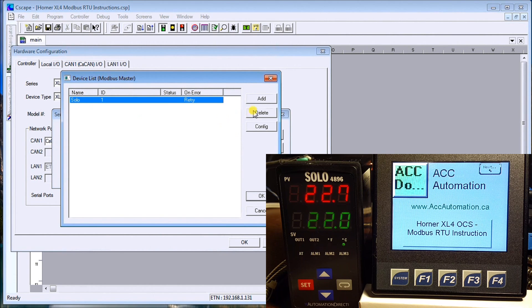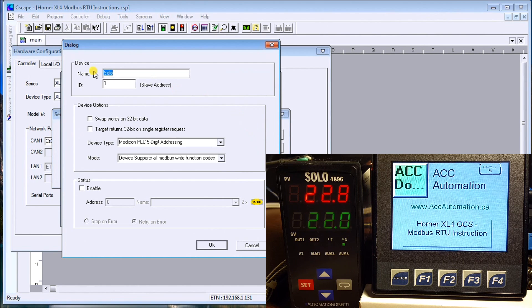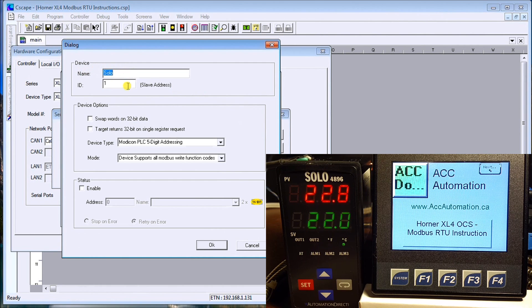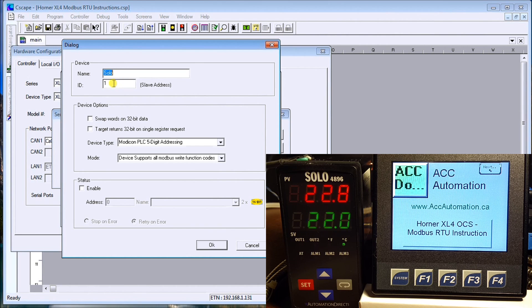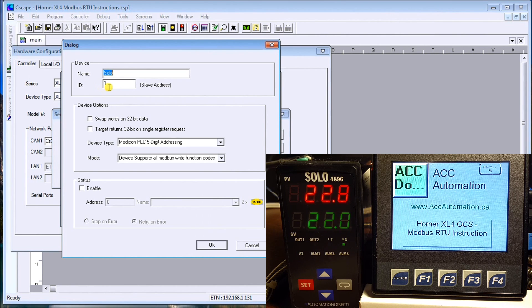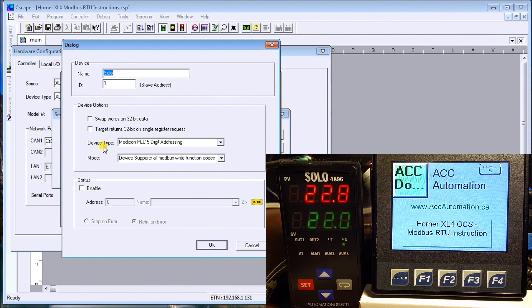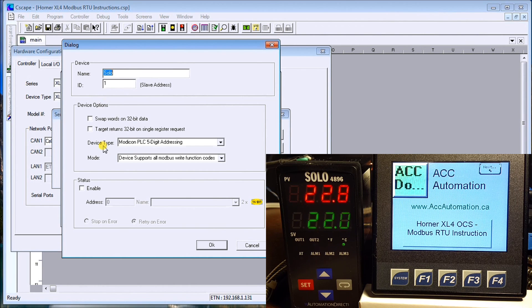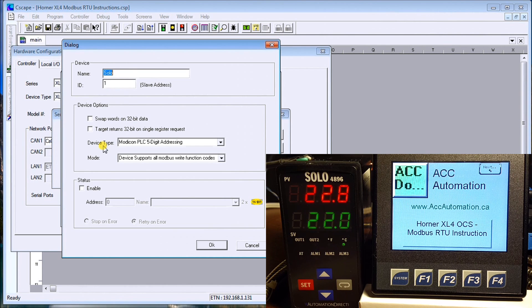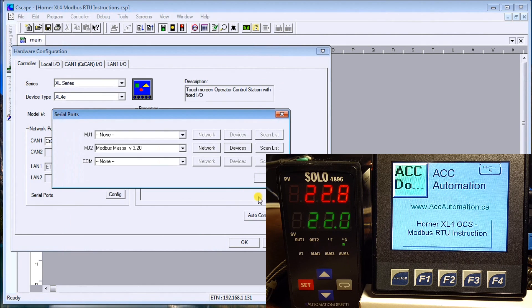On our devices, we'll just configure that one. We can add and assign a name to this as well as our slave address. We just set SOLO for one, which is unit number one. We could have up to 32 of these units on the same system. Our device type is Modicon PLC five-digit addressing, and that's what this SOLO will accept.